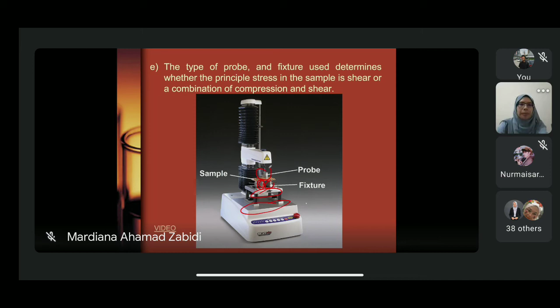You cannot put it directly on the platform, why? When you subject the sample to the compression of the probe, the risk is that the probe will pass through the sample and then compress directly onto the platform. That is what we do not want. So that is why we need this fixture in order to hold the sample. And this is the probe. The probe can be of different types. This one is an example of a probe.